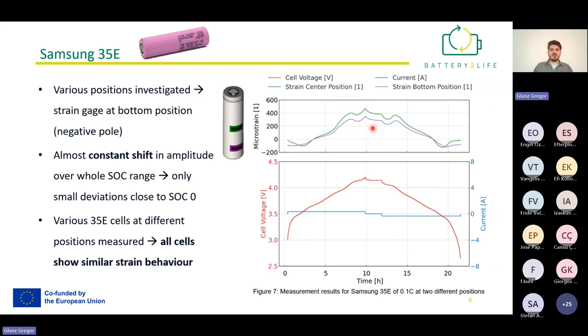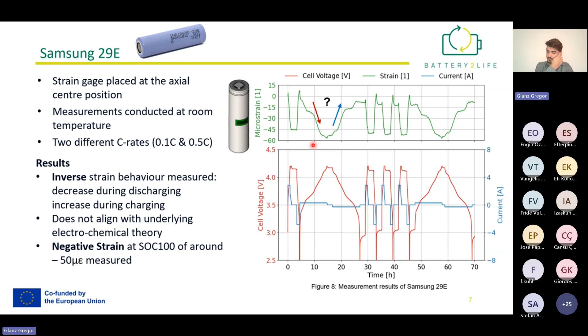However, coming now to the second cell type we investigated, this is the Samsung 29E cell. It's also from the type 18650. And we again placed our strain gauge at the axial center position, as you can see here in the schematic plot. And we did some very similar measurements. And for the 0.1 C charging and discharging rate, you can see here a decrease in strain during charging and an increase in strain during discharging. So basically the exact opposite or inverse strain behavior that we saw previously. And this strain behavior, however, does not align with the underlying electrochemical theory, and we even measured some negative strain.